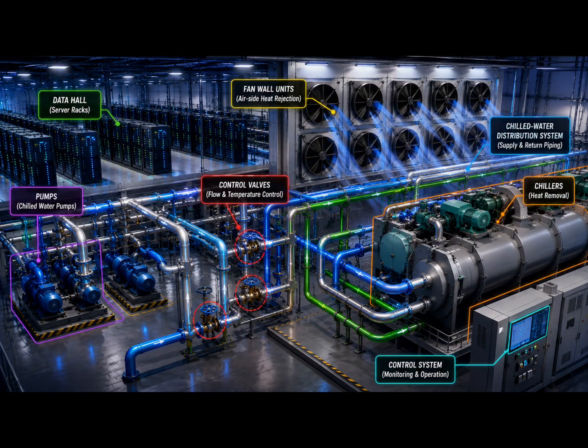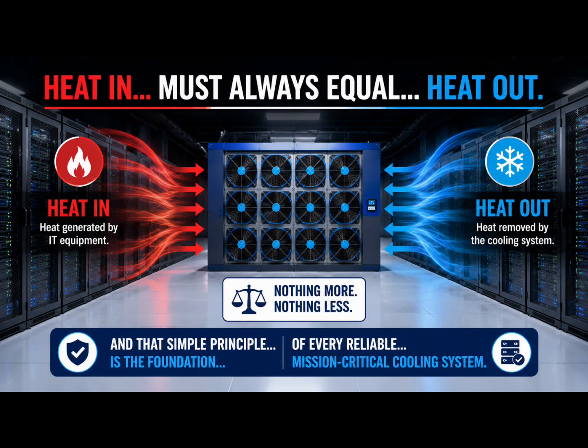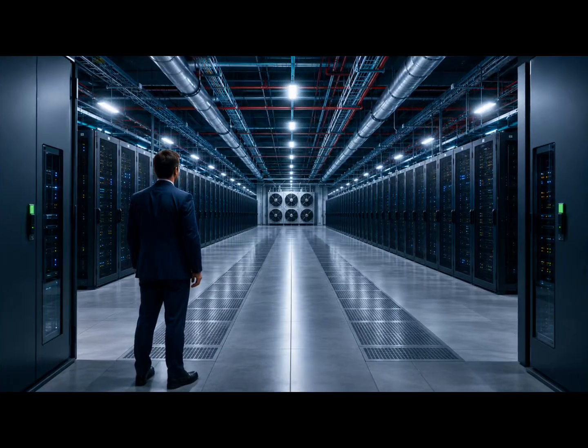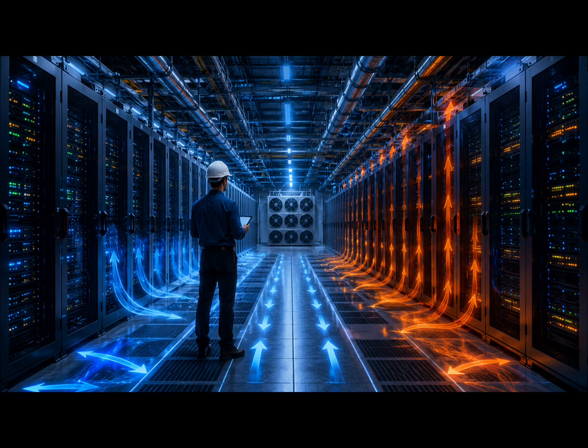Everything that follows, the pipes, the pumps, the chilled water system, the fan wall units, the control valves, and the chillers, is simply the result of one engineering calculation. Heat in must always equal heat out. Nothing more, nothing less. And that simple principle is the foundation of every reliable mission-critical cooling system. In the next chapter, we'll step inside our 8-megawatt data hall and begin calculating where every single watt of heat comes from. Now, let's step inside the facility.